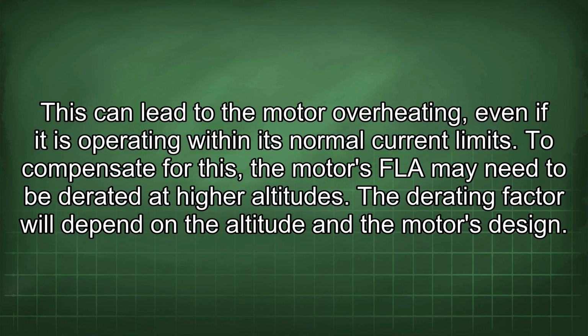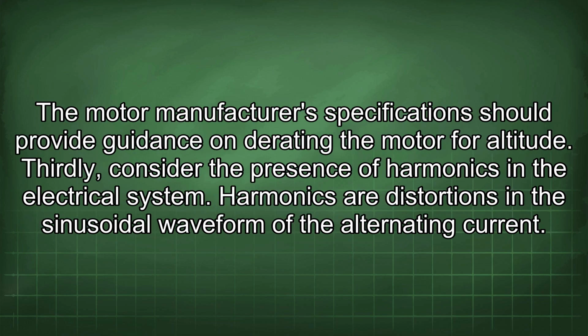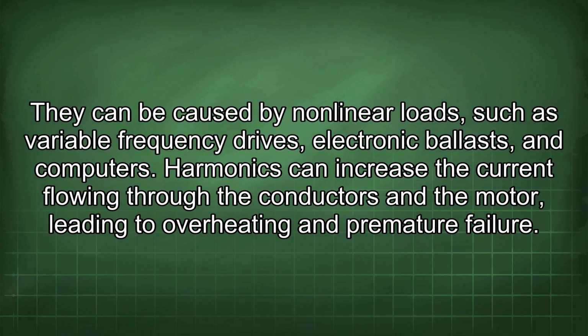The derating factor will depend on the altitude and the motor's design. The motor manufacturer's specification should provide guidance on derating the motor for altitude. Thirdly, consider the presence of harmonics in the electrical system. Harmonics are distortions in the sinusoidal waveform of the alternating current. They can be caused by nonlinear loads, such as variable frequency drives, electronic ballasts, and computers. Harmonics can increase the current flowing through the conductors and the motor, leading to overheating and premature failure.